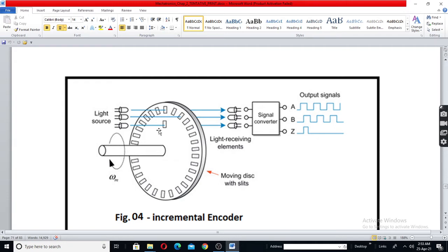the microprocessor has to wait till it receives the Z pulse. Then only it can count from that position. Say while starting the motor, the sensor was here, say at AB. This is somewhere at another place. It will have to ignore till it receives Z.